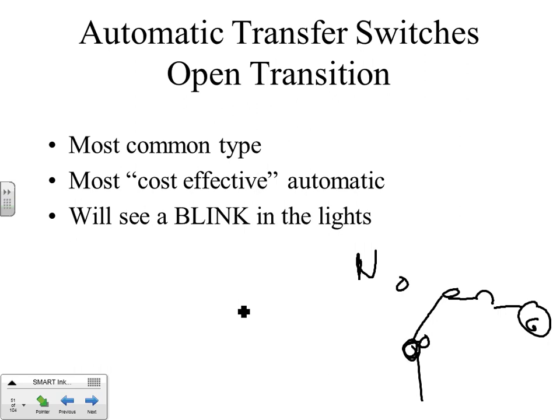Utility power comes back. The load is being supplied here. So the generator has got it, but now we're going to see a blink in the lights because this thing is going to transfer from here back to here, but it's going to be open for a certain period. It's about 100 milliseconds, but you'll see a blink in the light. And older computer systems had a tough time with that little opening. Pretty much corrected these days. They've gotten their power supplies a little better. You get a little more ride through. And that's also the most cost effective, cheapest. Cost effective is a nice word for that.